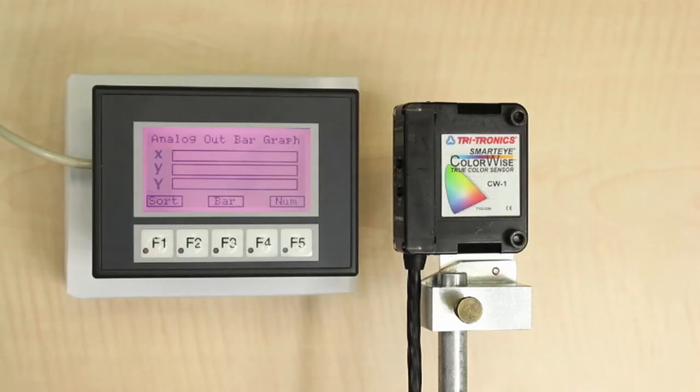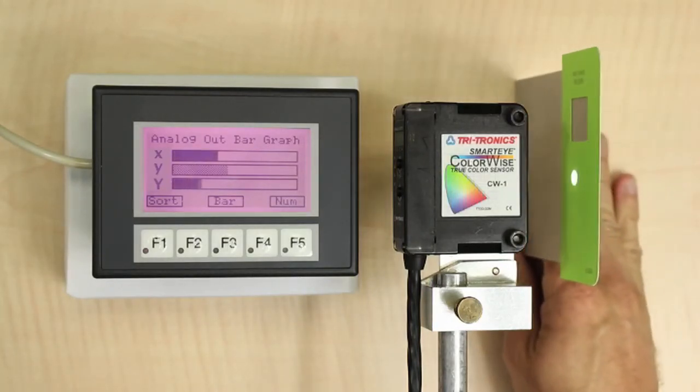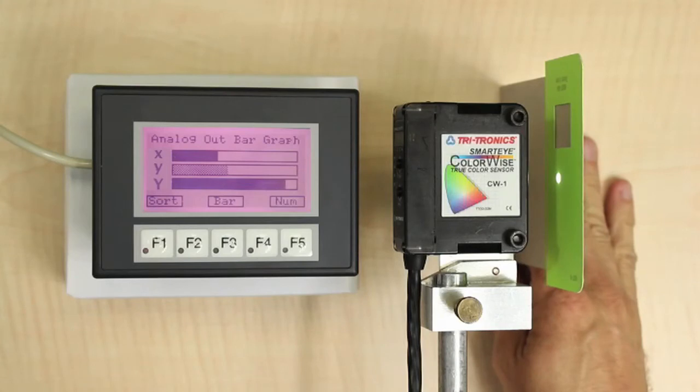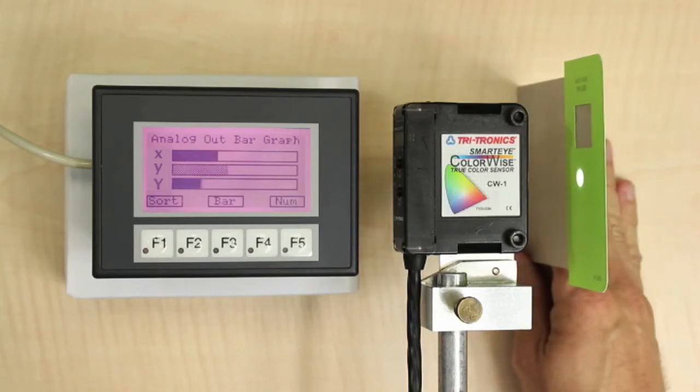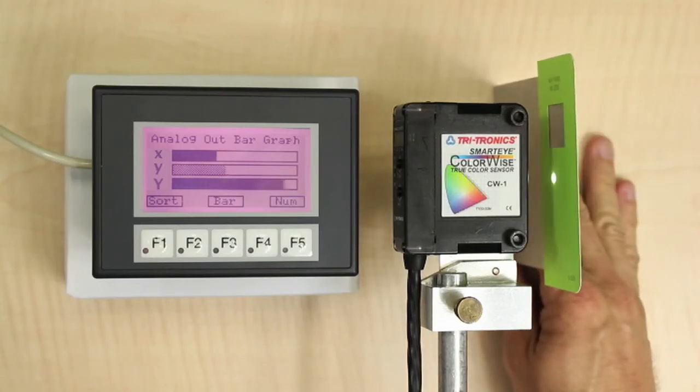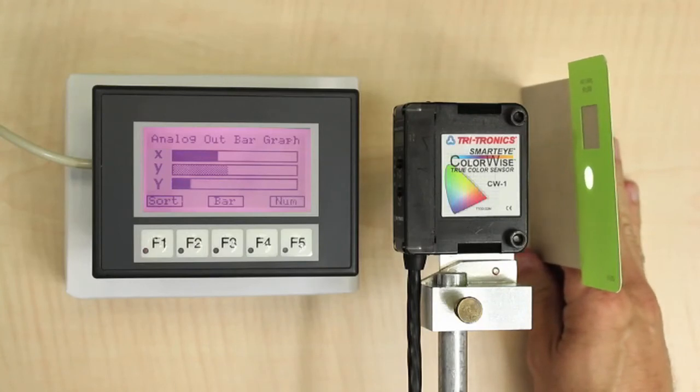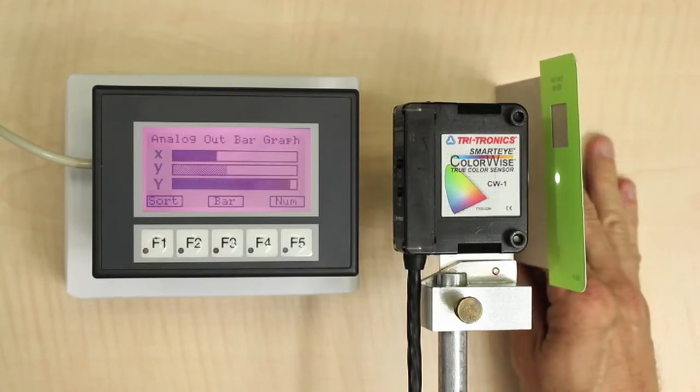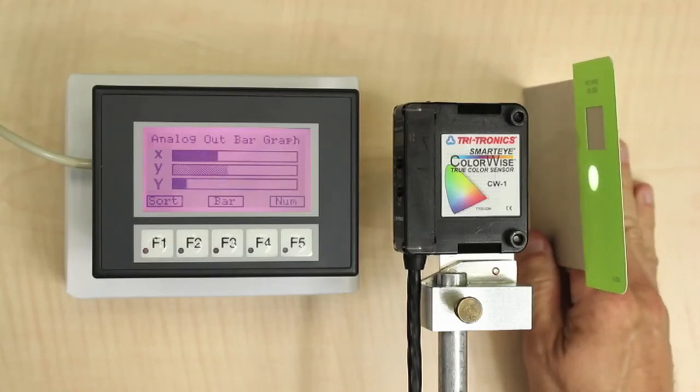Now let's consider the lime color as before. Here we see that the bar graph shows the XY coordinate values of the lime color. Note that as we change the distance to the target, we see that these remain essentially stable, and only the intensity bar changes. The stability of the XYY type output makes it a great choice for many applications.